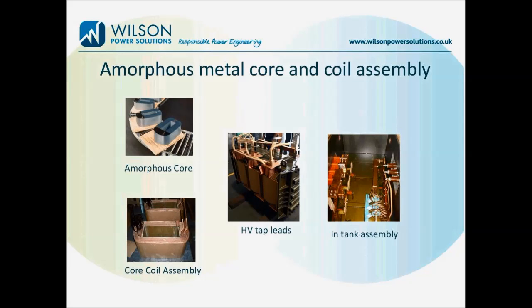Looking at these images here, the top left shows you that core loop we've just described, and then below where the HV and the LV coils have been fitted. You can see in that image on the right hand side the LV bars protruding there, and on the left the HV leads come out. Once that core coil assembly is complete, the image in the middle shows the construction with those HV leads coming out and leading off to the tap changer, the HV tap changer.